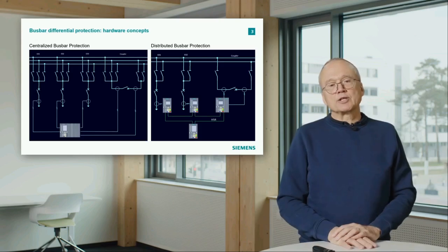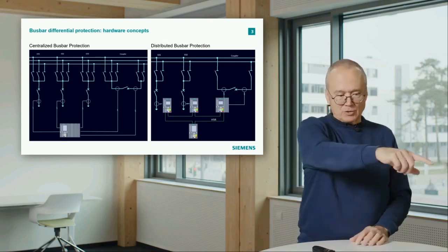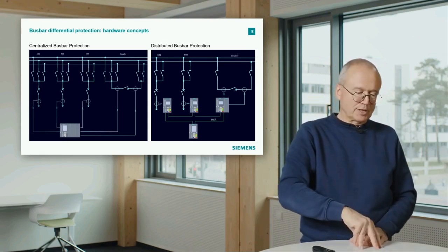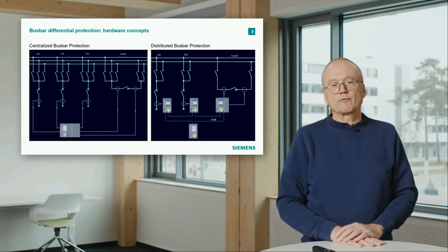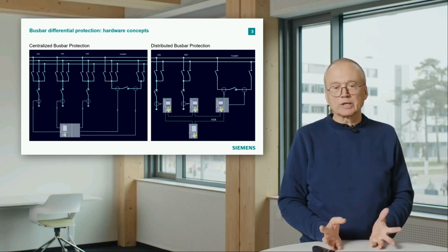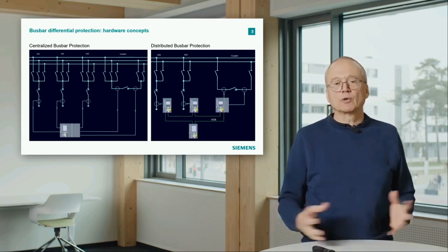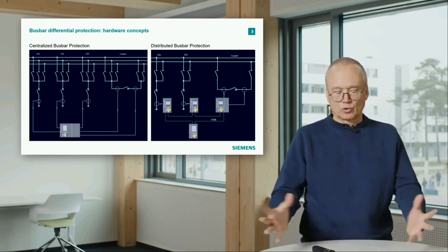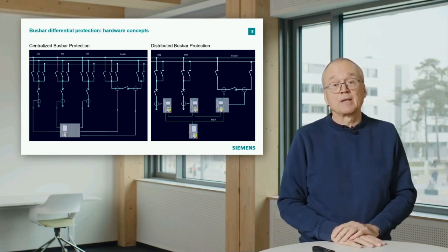In the previous generation, we had a star-connected setup. That means we had point-to-point connection from the central unit to all feeder units. With SIPROTEC 5, we now have this ring-type communication available because we make use of modern process bus technology. You need a redundant high-speed optical fiber, but it's powerful enough to bring all the sampled values to a central point, even for a bigger substation.